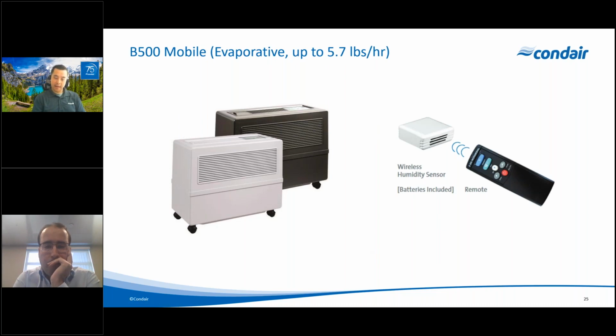The last technology we'll look at for in-space is a small packaged mobile evaporative system, what we call the B500. It's a wetted pad system, just like the ME, but in this case it's a standalone system. You can roll it into a small office or room if you want to humidify. Maximum capacity here is about 5.7 pounds an hour. We have options for supply water and drain water lines to be connected to automate it a bit, or a manual fill option where you periodically add water to the system. We do include a wireless humidity sensor and remote to control it and make it easier to operate.